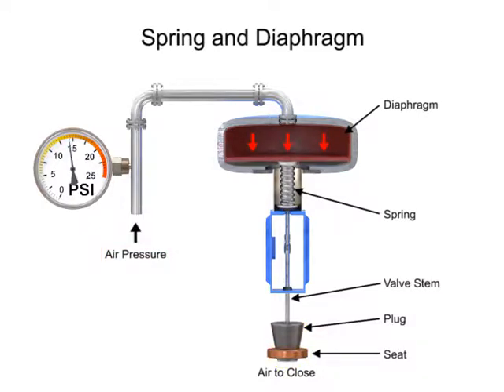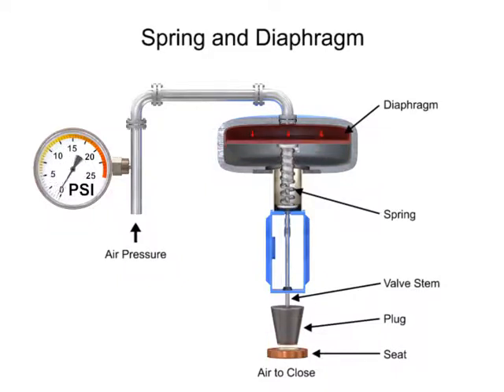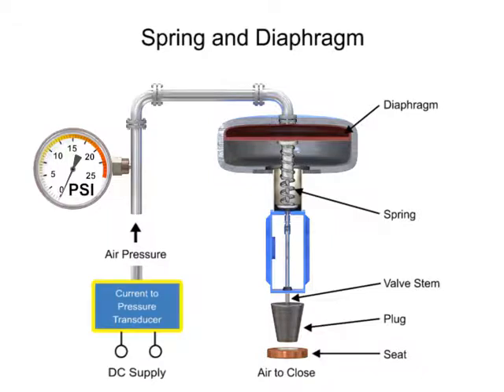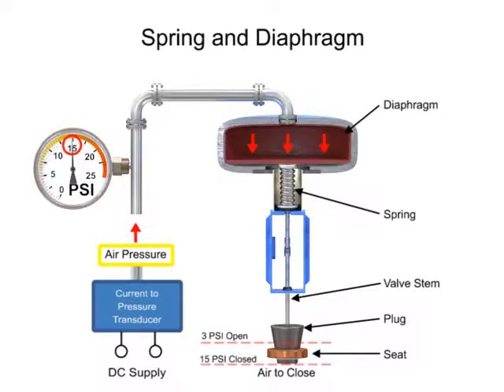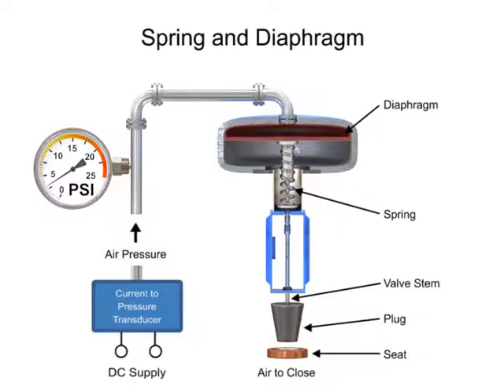With no air pressure, the restrictor is pushed upward by the spring to act as a normally open control valve. To vary the position of the restrictor and flow through the valve, a current to pressure transducer can be used to provide a 3 to 15 PSI signal to the diaphragm. At 3 PSI, the valve is maintained open, and at 15 PSI, the valve is maintained closed. Pressures between the 3 to 15 PSI range proportionally change the flow of the valve.